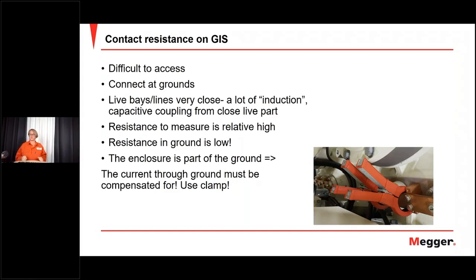But when you do resistive measurements, the resistance will get relatively high because you're not only measuring the actual breakpoint, you will also measure the bars and the different components between your connection point and the circuit breaker, and on both sides, right? And as I said, resistance in ground is low, so that makes it even more trouble. The whole enclosure is part of the ground. That's what makes the trouble. So in this case, you must compensate.